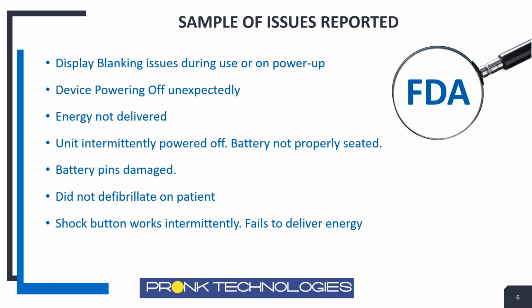The shock button working intermittently. Lots of incidents reported about the shock button not functioning properly. So these are just a sample of common issues reported to the FDA, and it brings to light the importance of testing and really going through what we need to do to perform all of the things necessary to feel confident to put the device back into service.